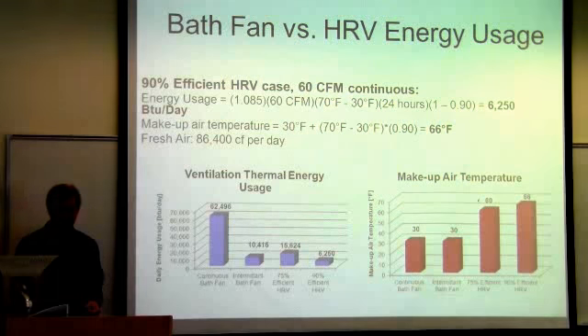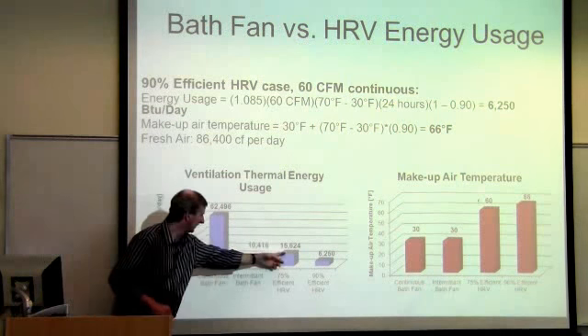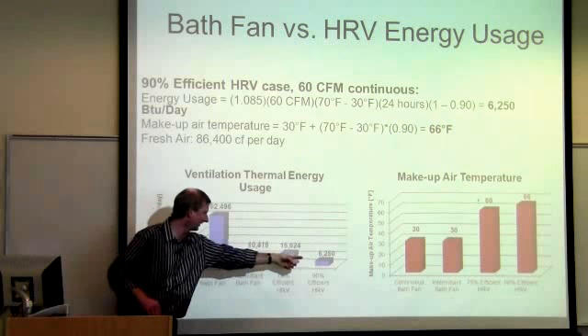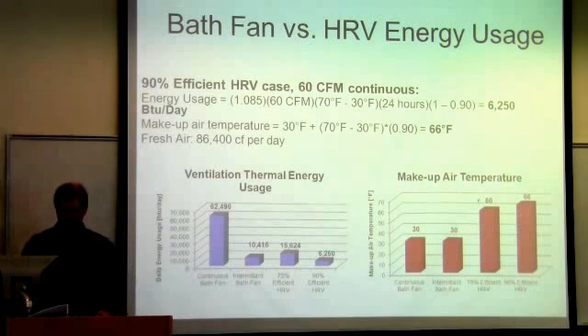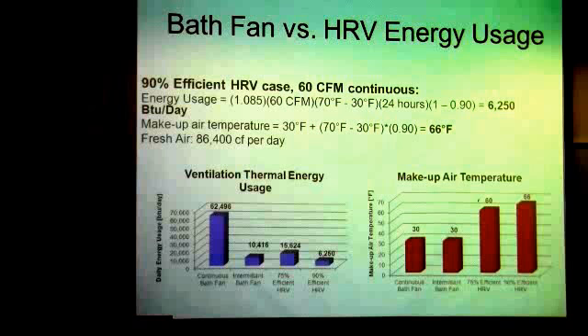And then if you go up to 90%, you drop from 15,000 BTUs for heating the makeup air down to 6,000. So it kind of just gives you an example of the old way of just using the exhaust fan. But as houses get tighter and tighter, you need to make sure you get at least 0.2 air changes, which is ASHRAE, the 0.2 air changes. You prefer 0.3 air changes, and to get that takes a lot of makeup air. So the HRV helps you prevent having to heat it. It heats it using the exhaust air. I think that's all I had.